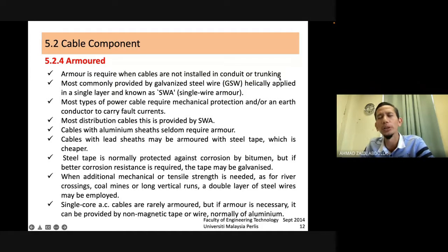So let's say you want to design a cable from SSB to MSB, which the MSB is located in another block. So when you have that situation, you must use the underground cable kan. You cannot let the underground use conduit or trunking. So when you want to lead the cable underground, you need to use cable that comes with armoured cable. Okay, so most commonly provided by galvanized steel wire. So tak ada picture dia. It has a steel wire at the outside of the cable. Okay, helically applied in single layer, known as SWA.